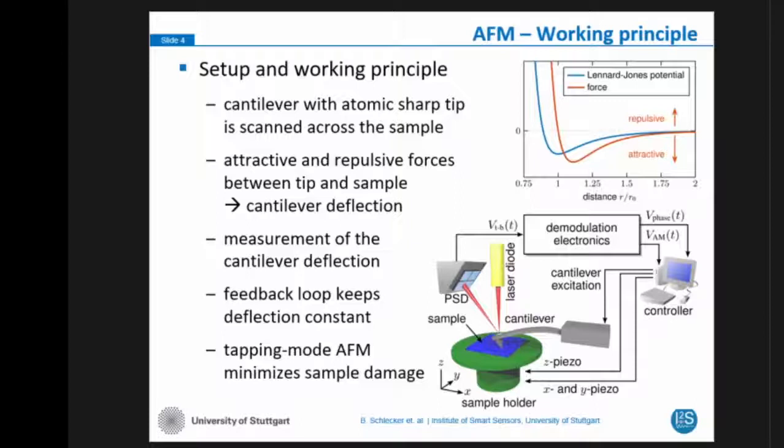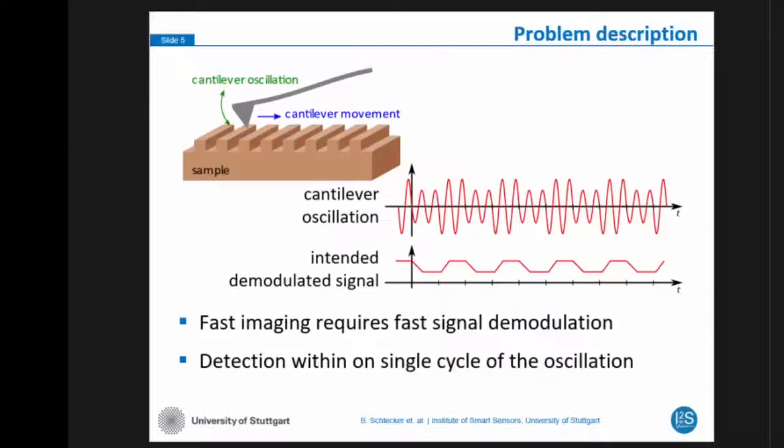The demodulated signal is fed to the AFM controller and fed back to the cantilever in order to keep a constant deflection of the cantilever by means of adjusting the height of the sample with a Z-piezo. In bio-applications, we usually work in the tapping mode AFM, which reduces the forces which act on the sample.